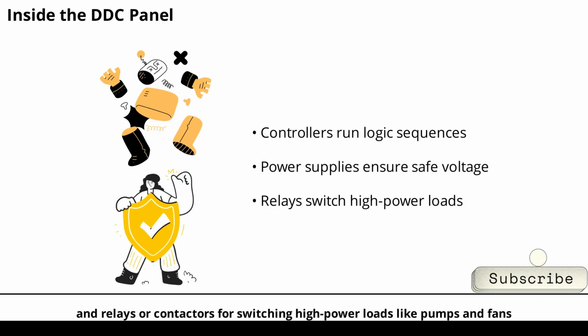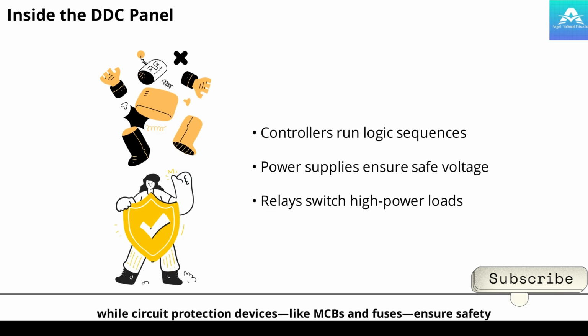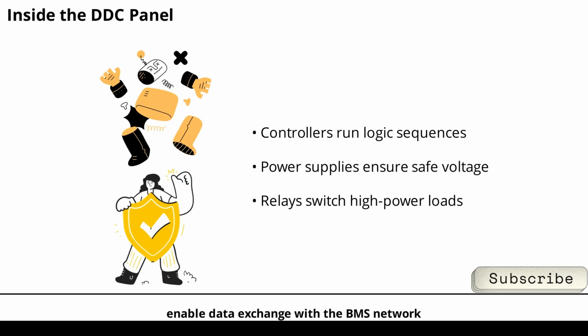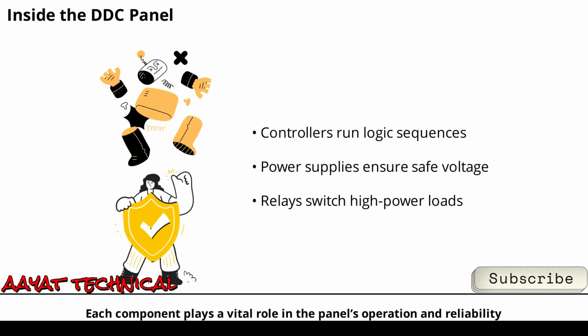Terminal blocks keep wiring organized, while circuit protection devices like MCBs and fuses ensure safety. Communication devices, such as routers or RS485 interfaces, enable data exchange with the BMS network. Cooling fans or vents help maintain optimal temperature inside the panel. Each component plays a vital role in the panel's operation and reliability.